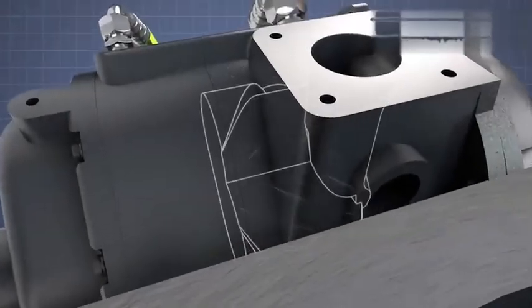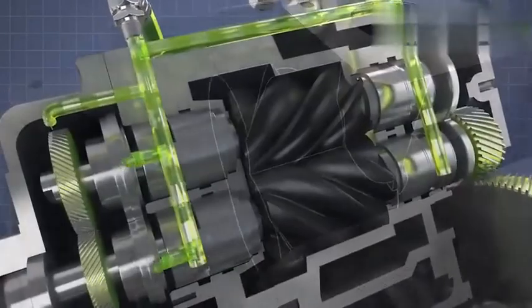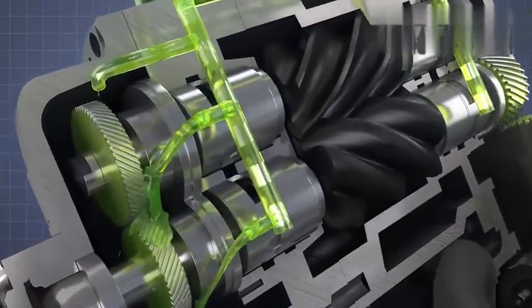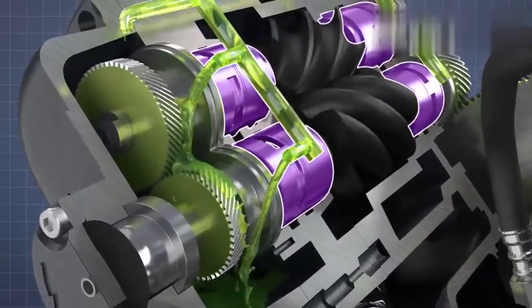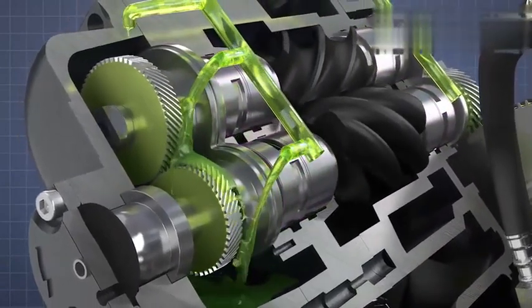Oil never enters the compression chambers but is used to keep gears and bearings lubricated and cool. Special seals between the rotors and bearings prevent air passing into the oil system and oil passing into the compression chambers.